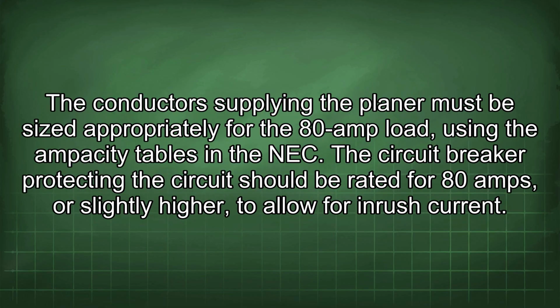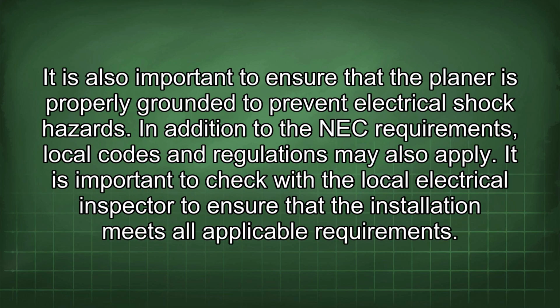The conductors supplying the planer must be sized appropriately for the 80 amp load, using the ampacity tables in the NEC. The circuit breaker protecting the circuit should be rated for 80 amps, or slightly higher, to allow for inrush current. It is also important to ensure that the planer is properly grounded to prevent electrical shock hazards.